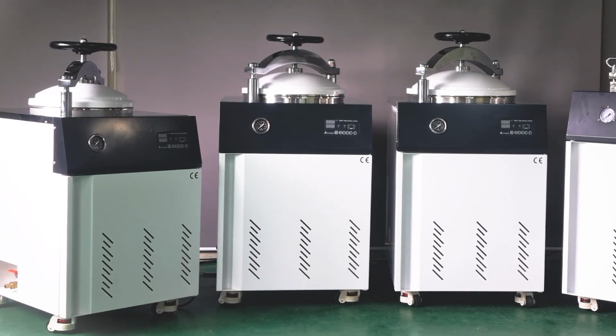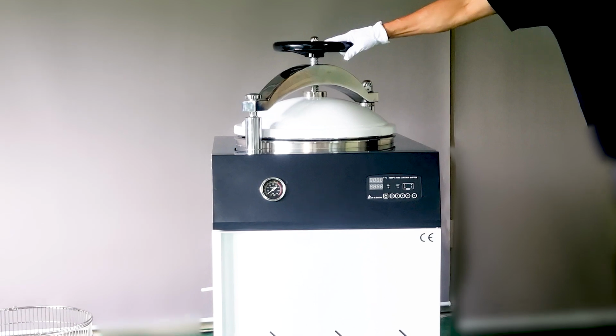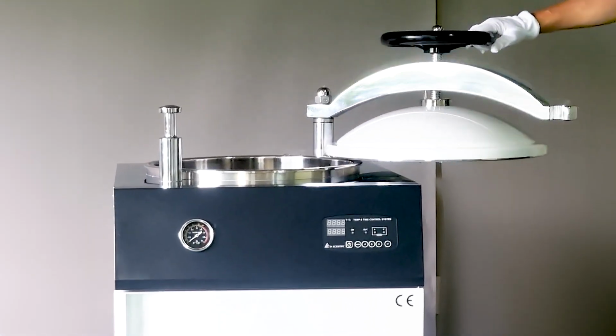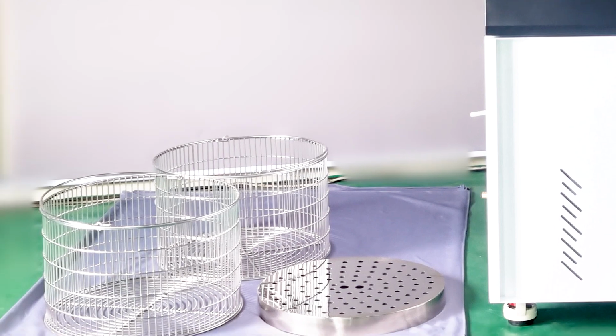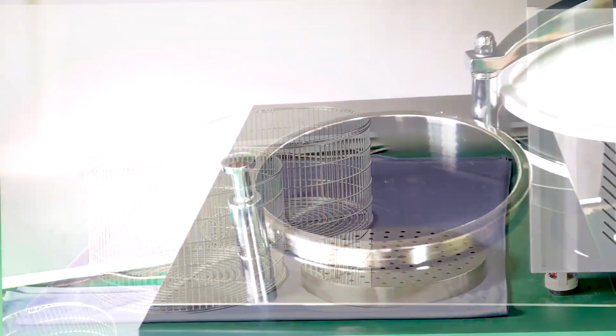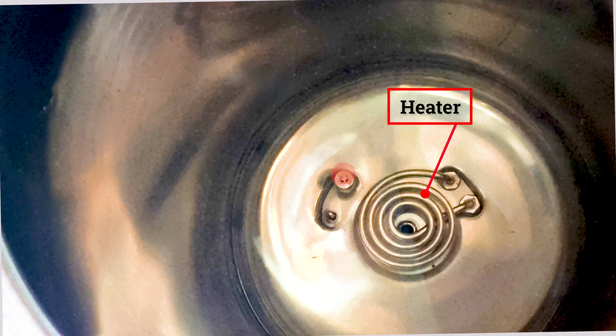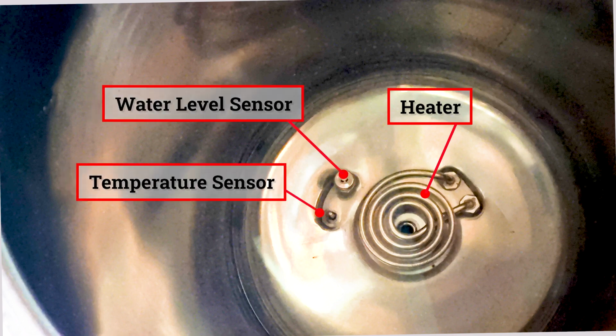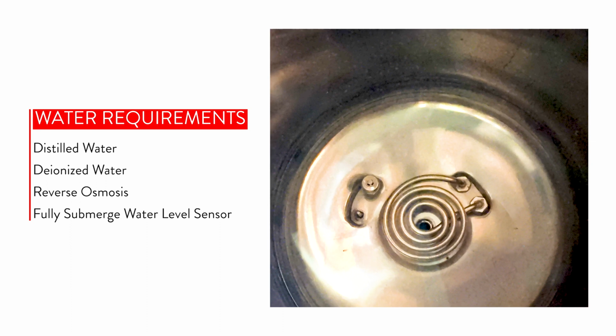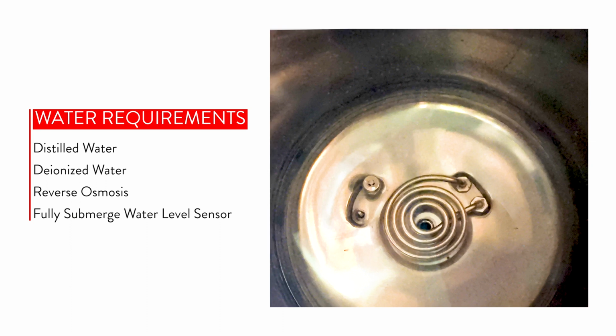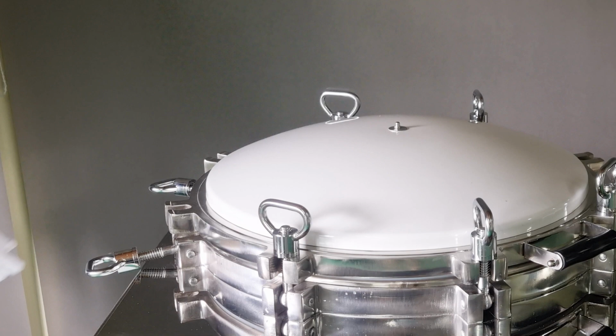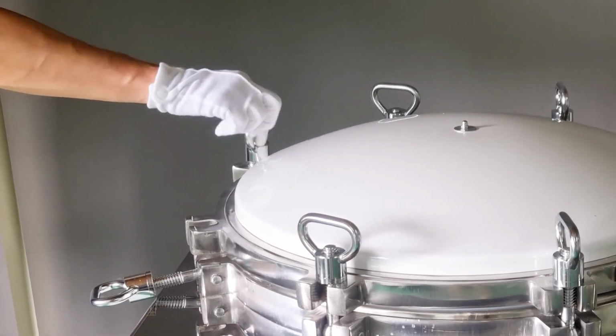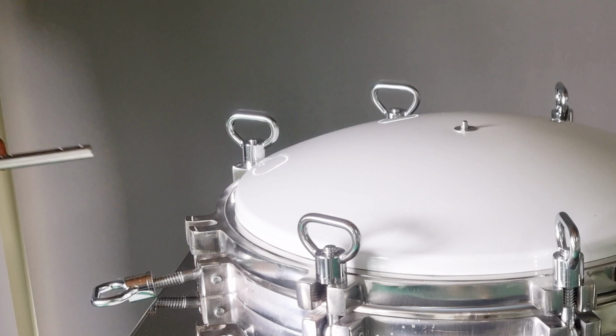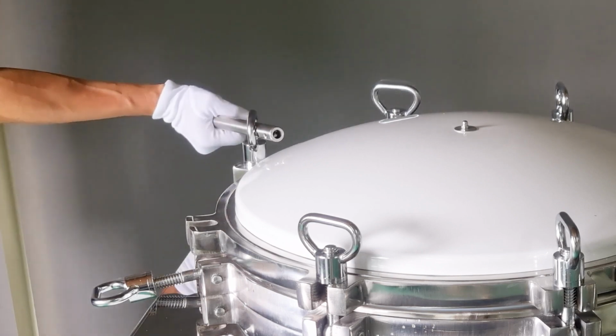On the 60, 80, and 100-liter models, simply turn the handle counterclockwise to open the door. Inside are 2 wire baskets and 1 heater cover. You'll also find heaters, a water level sensor, and a temperature sensor on the bottom of the chamber. Please make sure to only use distilled, deionized, or reverse osmosis water, and make sure the water level sensor is fully submerged. Note that the door on the 150-liter model closes with bolts and a fastening bar. These are extremely strong, and they fit precisely, so please don't fasten them too aggressively.